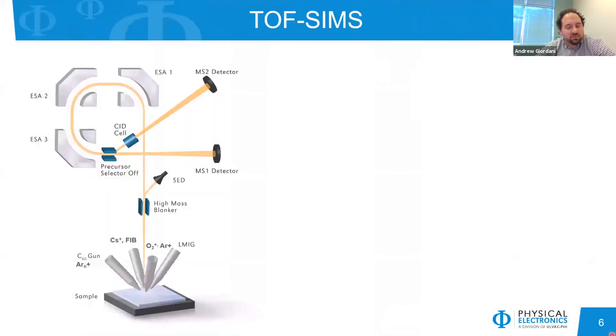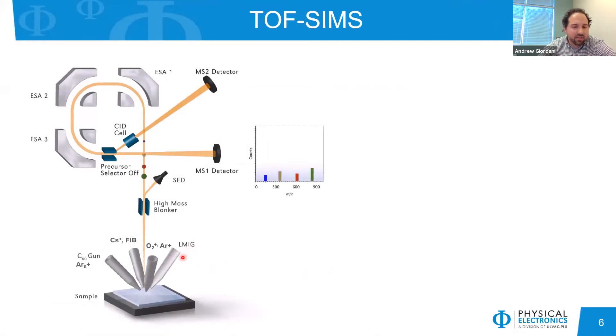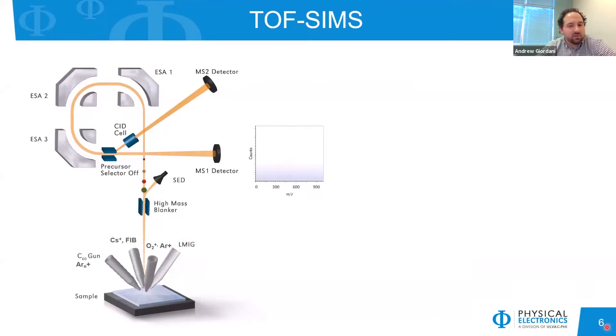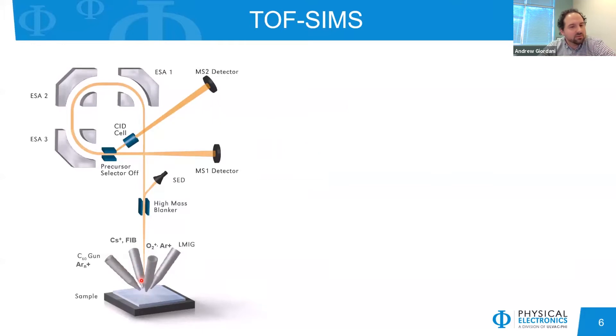TOF-SIMS takes a pulsed ion beam, bunches it to about a nanosecond pulse width, and then bombards the sample surface. Secondary ions are generated and extracted at roughly 3 kV. As they're extracted at the same nominal energy, they go through the drift spectrometer through three ESAs, and they are energy compensated, beginning to time-separate the ions based on their mass-to-charge. Lighter ions hit the detector first, followed by heavier ones. The mass spectrum shows the green peak corresponding to a higher mass-to-charge compared to the blue one, and it repeats as it rasters across the sample. There are also multiple other ion beams that can be used.